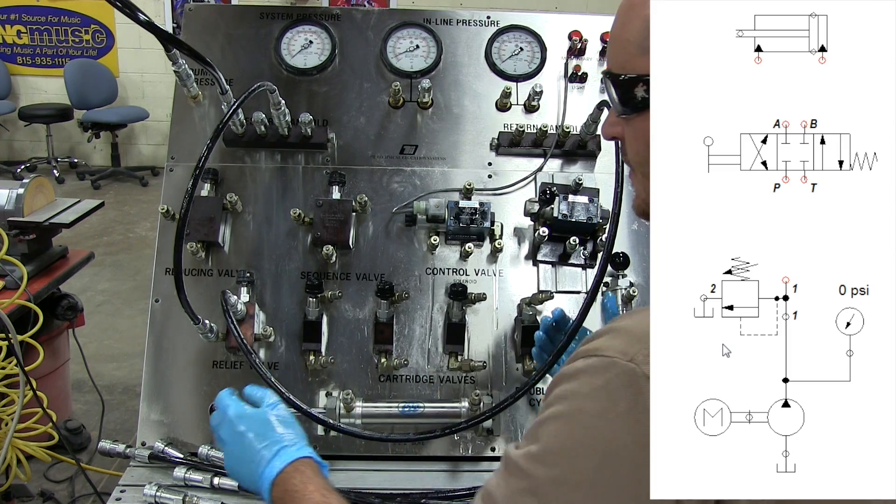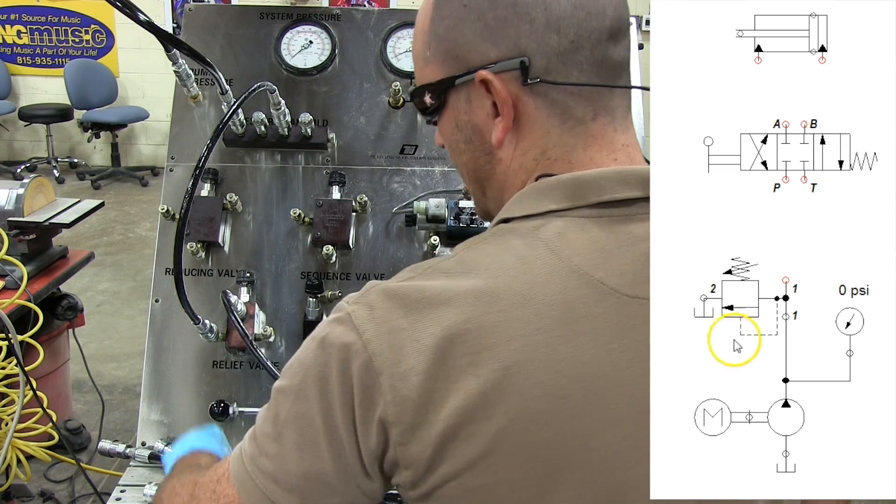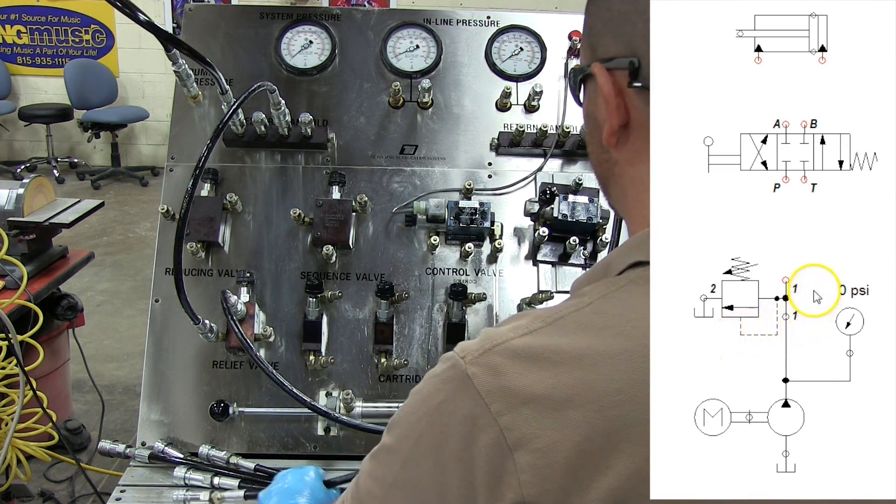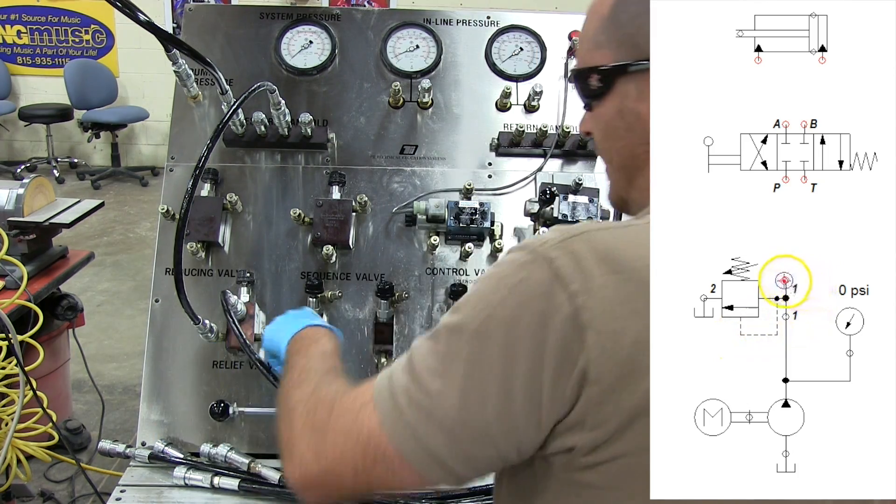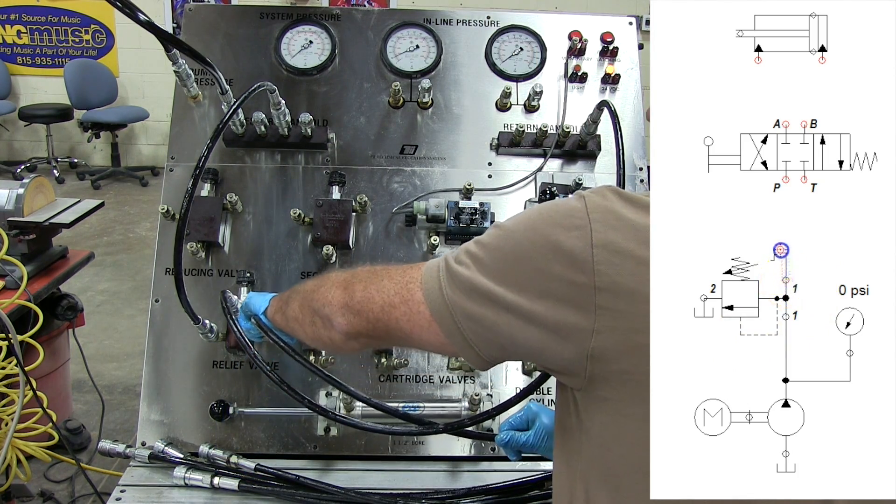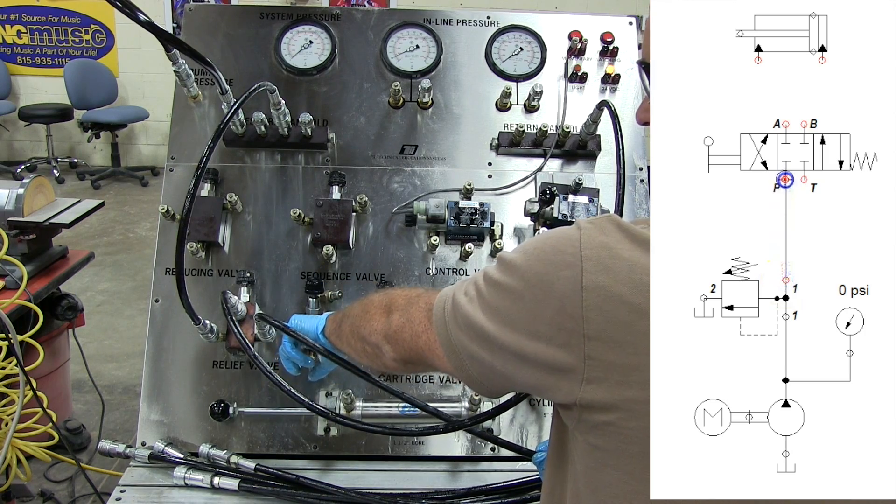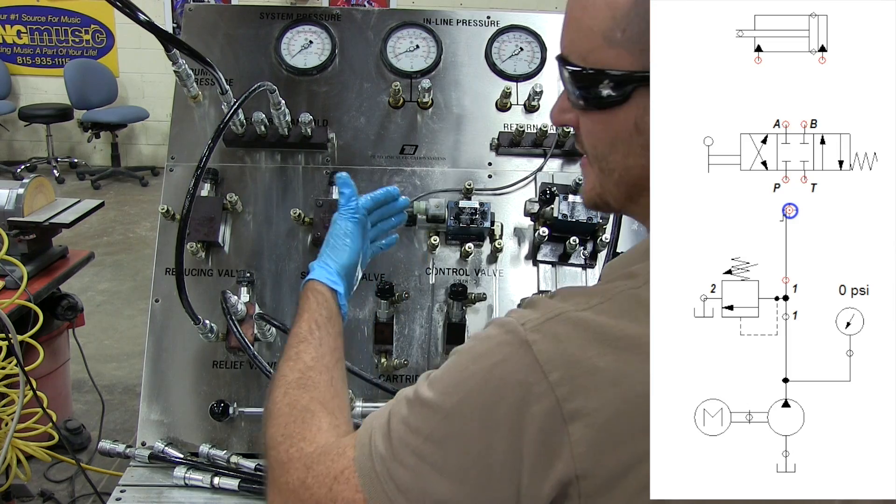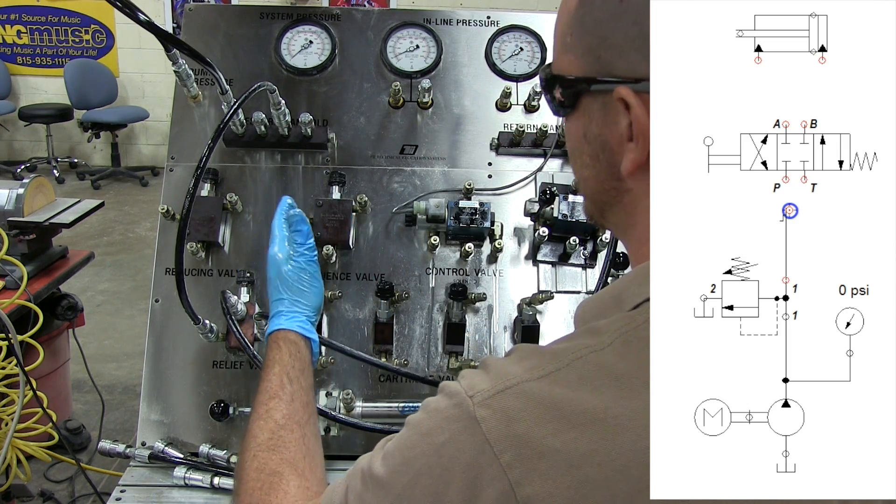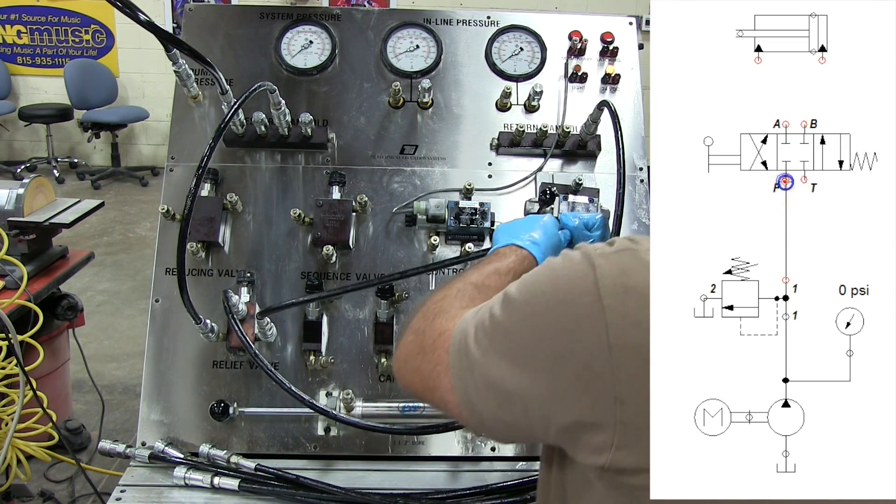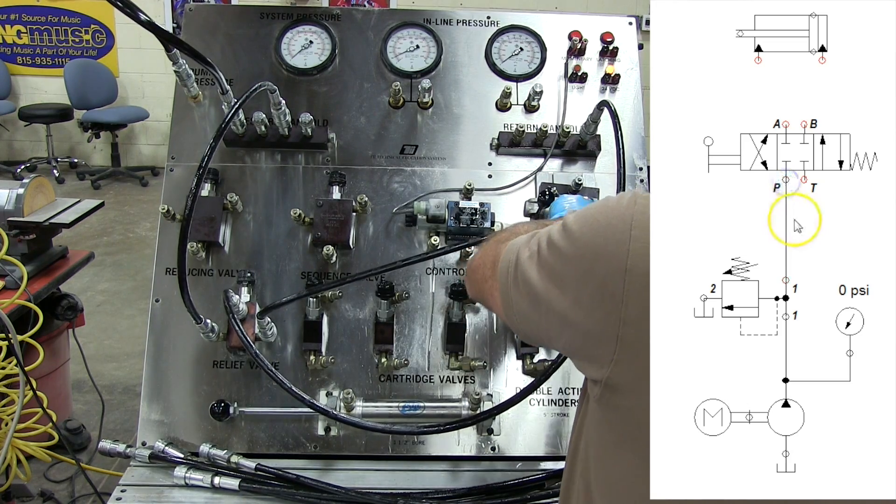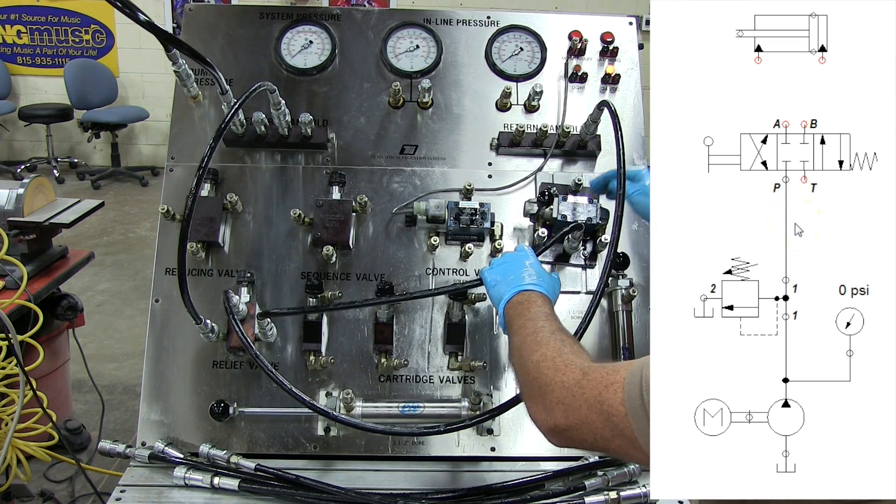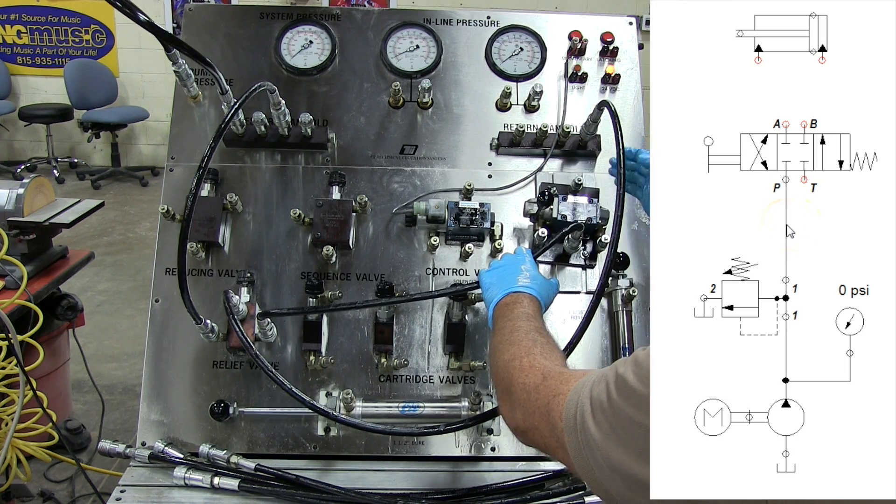Now what we want to do here is we want to take advantage of that internal T. So from this T, what we're going to do is we're actually going to go ahead and hook up to the pressure port of the directional control valve. So I'm bringing it from that T, which sometimes is represented by a dot, sometimes it's not, it's just a T in the actual diagram, and I'm running this over to the pressure port on my 4-3 lever controlled valve.